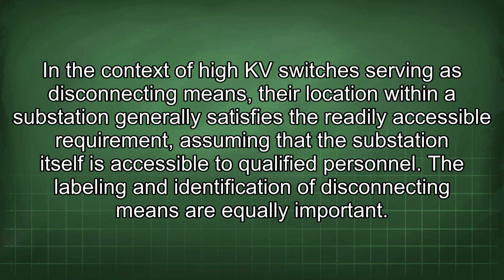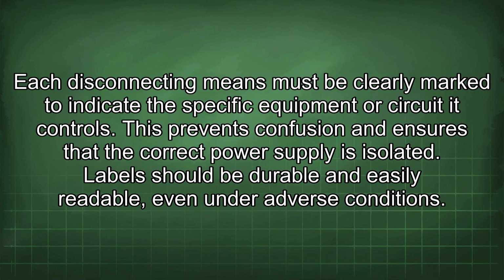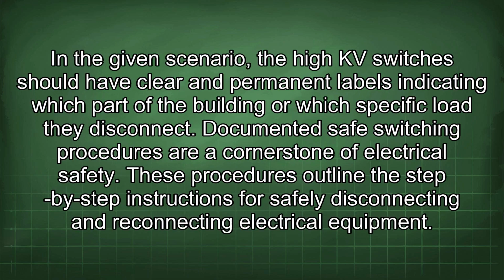The labeling and identification of disconnecting means are equally important. Each disconnecting means must be clearly marked to indicate the specific equipment or circuit it controls. This prevents confusion and ensures that the correct power supply is isolated. Labels should be durable and easily readable, even under adverse conditions. In the given scenario, the high kV switches should have clear and permanent labels indicating which part of the building or which specific load they disconnect.